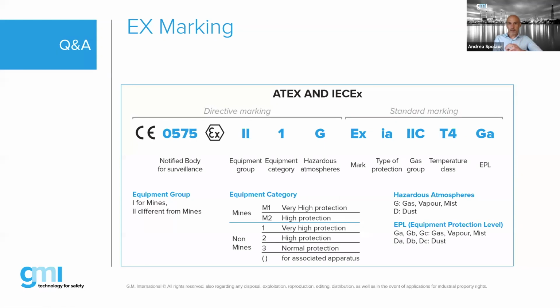So let me give you a quick overview of the difference. 1G in this case means Ga, as you see at the end of this marking. Ga is for the IECEx application, 1G is for ATEX, and I think it means the same. G stands for gas, and 1 is the very high protection level. So it's the same as Ga: G means gas, and A is the most dangerous area for gas. After that there is Ex ia, which is the type of protection, in this case intrinsically safe. Then IIC is the gas group, and T4 is the temperature class, which can be from 1 to 6.